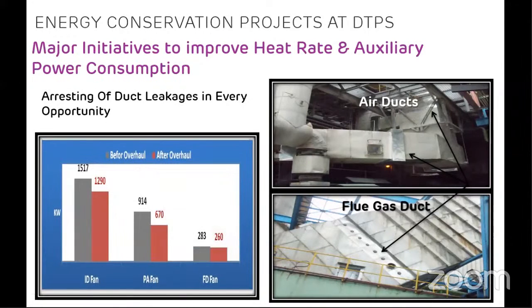Then the next major energy conserving initiative: in every overhaul, we observe that there are some leakages in air ducts, which we monitor during running of the plant. During the shutdown or overhauling, we attend to these air duct or flue gas duct leakages, which reduces the loading of the primary air fan, forced draft fan or induced draft fan. So loading of these fans is reduced and therefore there is saving in energy.